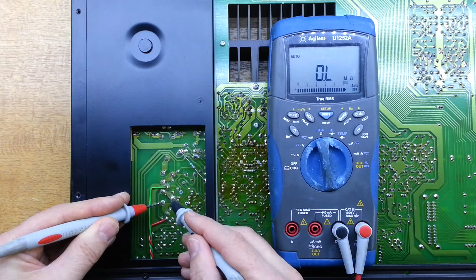Now, if our problem was on the positive side, and if I measure between the AC point of the rectifier and the positive side, that's reading a short. So both AC points to the positive outputs are short, and to the DC, the negative point, that's reading just fine. So either half of that rectifier's gone, or we've got a problem with the windings.